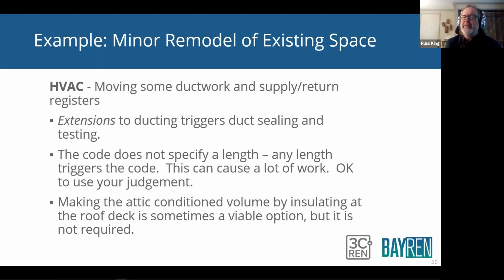Duct sealing in commercial buildings is kind of a pain. I've watched it, I've monitored it, I've tested it. Duct testing in a commercial building is kind of a pain because you have to seal off all the supply registers. And these registers are just sitting in a T-bar ceiling and they're really difficult to seal so that you can pressurize the ducts to measure the leakage. Also, they're usually not very well connected to the back of the registers and stuff like that. So duct testing in commercial buildings is kind of a pain. It's a lot of work.